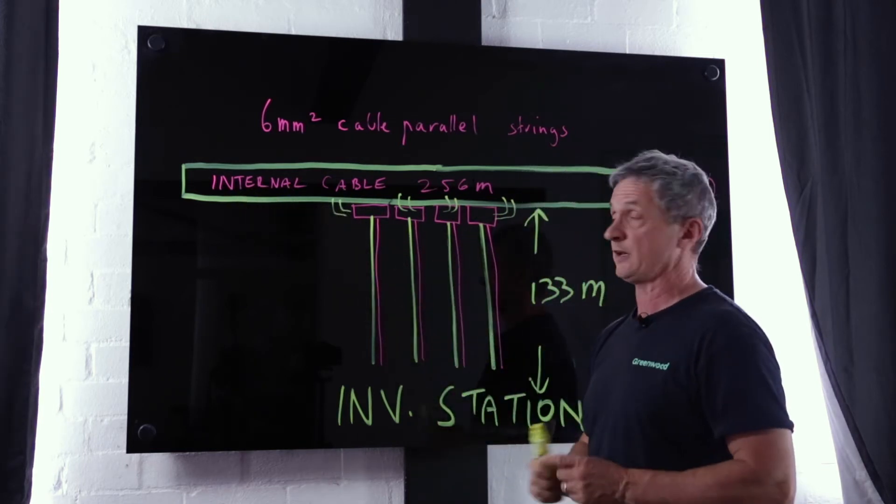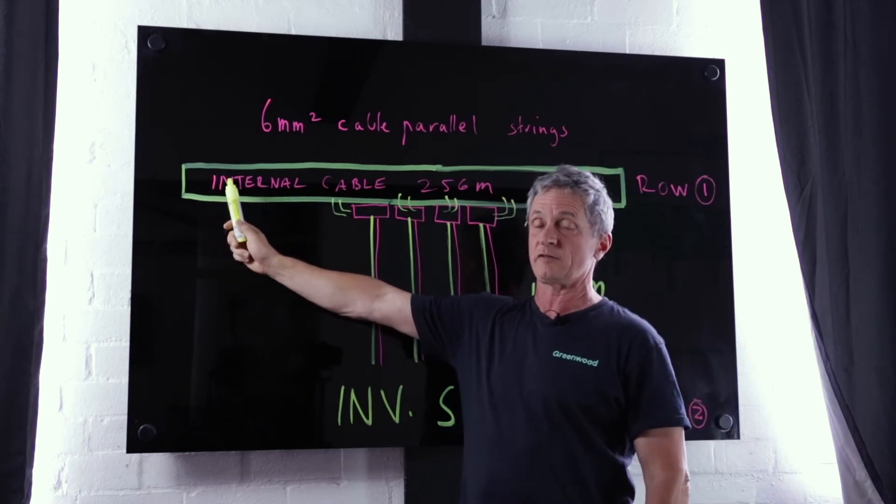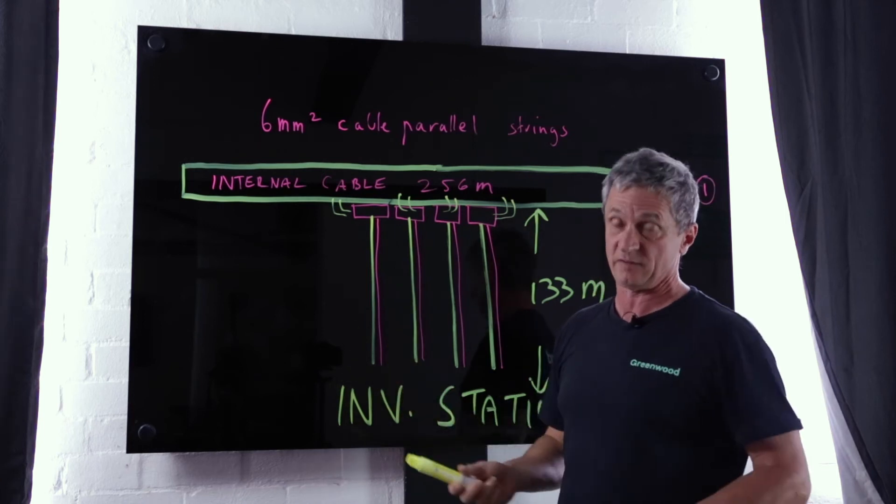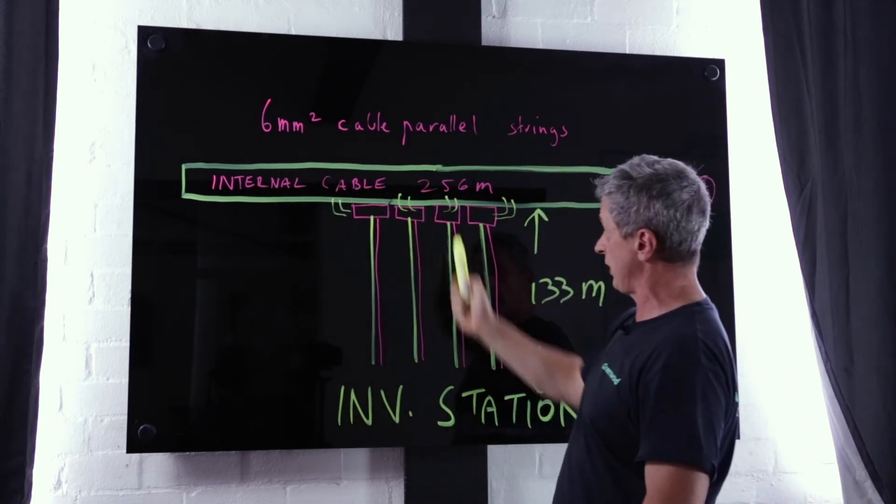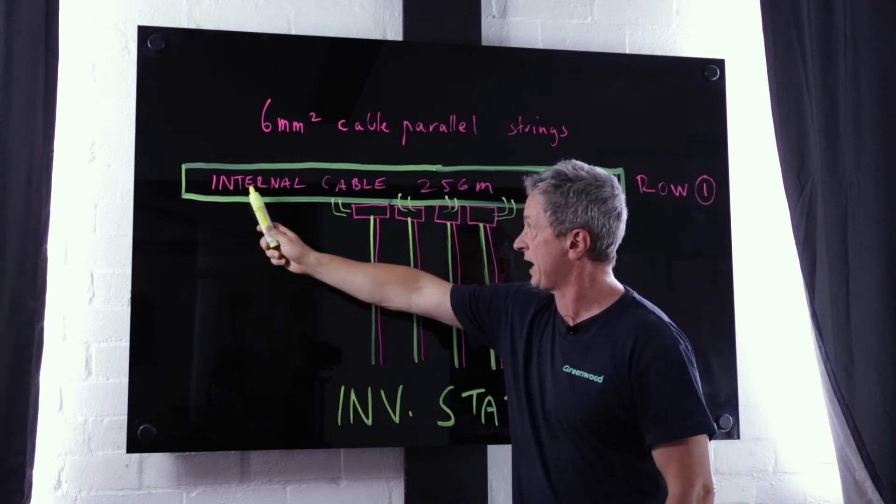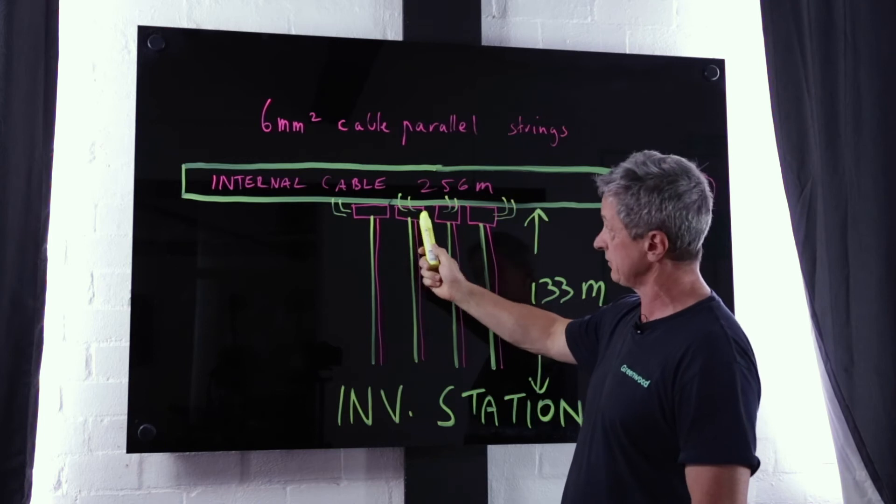But in this case we are stopping here and doing a connection at the DC isolator. So we have to do two calculations. We have to do the volt drop here and the internal volt drop here.